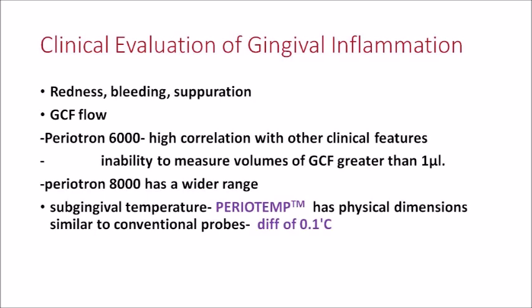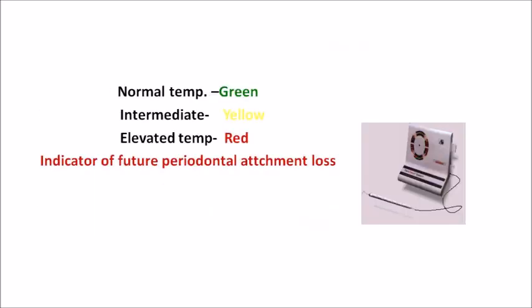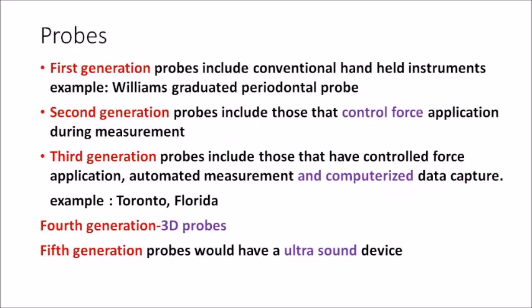That is why Periotron 8000 came into being — it has a wider range. Next is subgingival temperature, another clinical feature. The instrument is Periotemp, which has physical dimensions similar to a conventional probe. When inserted into the pocket, it can detect a difference of up to 0.1 degrees Celsius. Normal temperature gives a green color, intermediate gives yellow, and elevated temperature gives red — indicating future periodontal attachment loss.